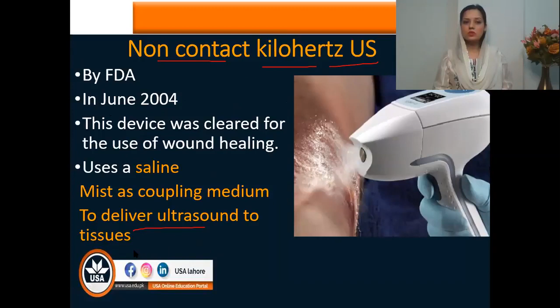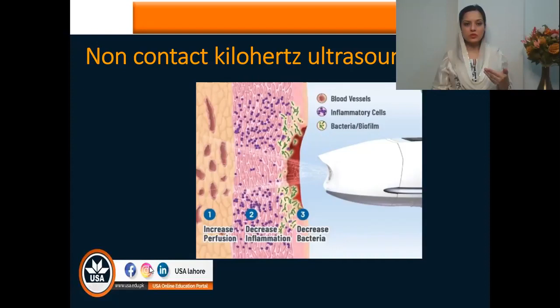The treatment duration for non-contact kilohertz ultrasound depends upon the area of the wound. If the wound is smaller than 10 square centimeters, we can apply it for 3 minutes. If it is 10 to 19 square centimeters, we apply it for 4 minutes. The time increases by 1 minute for each additional 10 square centimeters. So depending upon the size, you apply it according to the time duration.